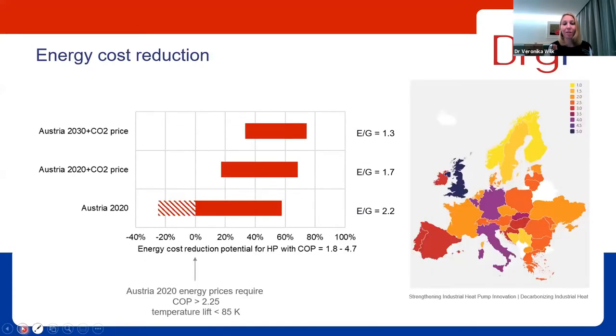Another important part of the discussion is, of course, the economics. And again, starting from the bottom, this is Austria today. If we take those average industrial prices, we have to make sure today that the heat pump does not require a temperature lift that is higher than 85 K, because then we will pay more for the operation of the heat pump than a natural gas burner.